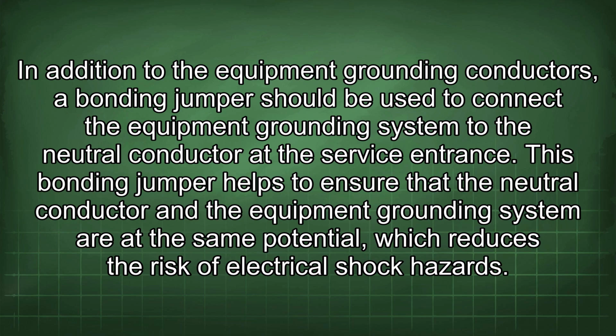In addition to the equipment grounding conductors, a bonding jumper should be used to connect the equipment grounding system to the neutral conductor at the service entrance. This bonding jumper helps to ensure that the neutral conductor and the equipment grounding system are at the same potential, which reduces the risk of electrical shock hazards.